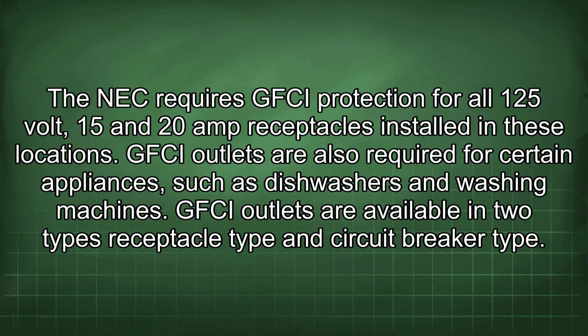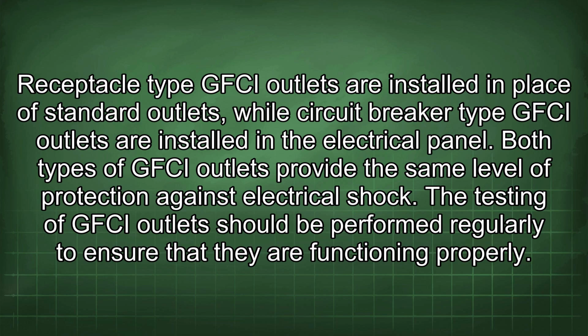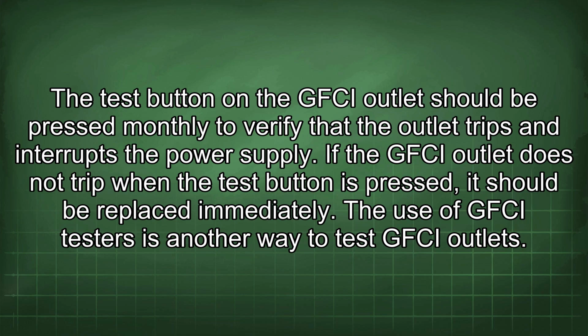GFCI outlets are available in two types: receptacle type and circuit breaker type. Receptacle type GFCI outlets are installed in place of standard outlets, while circuit breaker type GFCI outlets are installed in the electrical panel. Both types of GFCI outlets provide the same level of protection against electrical shock. The testing of GFCI outlets should be performed regularly to ensure that they are functioning properly. The test button on the GFCI outlet should be pressed monthly to verify that the outlet trips and interrupts the power supply. If the GFCI outlet does not trip when the test button is pressed, it should be replaced immediately.